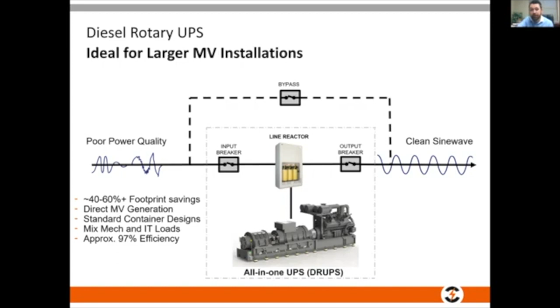And then finally, we are able to mix our mechanical or IT loads. Again, we can put it at the substation. And all of this is a very high efficiency of 97%. What I'm not saying is my machine is 97%. I'm saying the system from the input to the output is 97%. And I do have a slide slightly later in the presentation that makes comparison back to static UPS there. They're very much my best guess. So please stop me and correct me where I'm wrong. But you'll see that our efficiencies are very high.